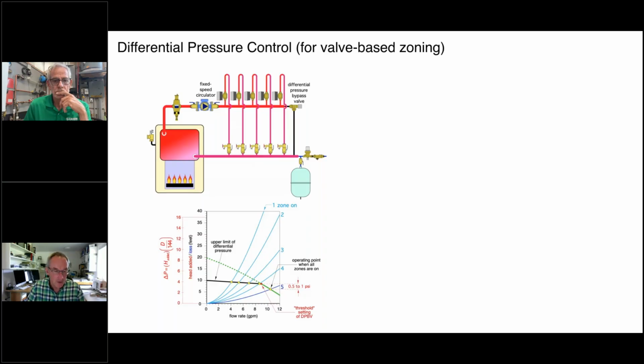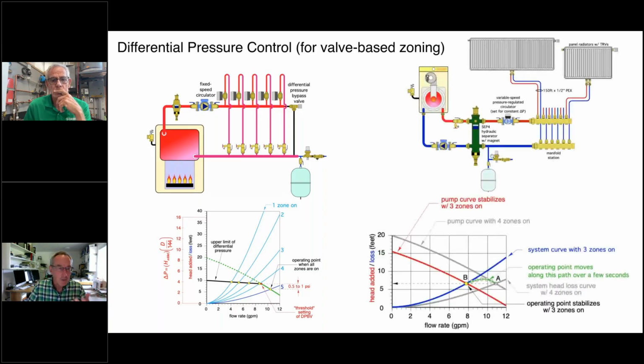It was acceptable and it worked, but today we have variable speed circulators, many of which have what's called a constant delta P or constant head setting. The way that works, let's start with these 2 gray curves. The lower curve is a system curve with 4 zones on, and the gray curve I'm pointing the cursor at is the pump curve. So we've got an operating point here at about, say, 11 gallons per minute. Well, let's say we close a zone down. It could be any valve-based zone: an electric zone valve, a thermostatic valve, anything that closes the flow off.